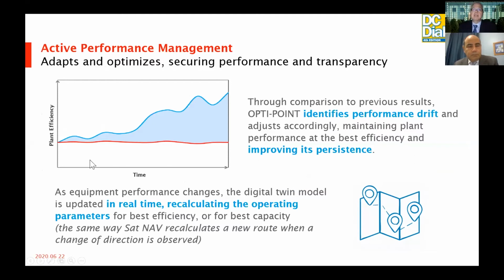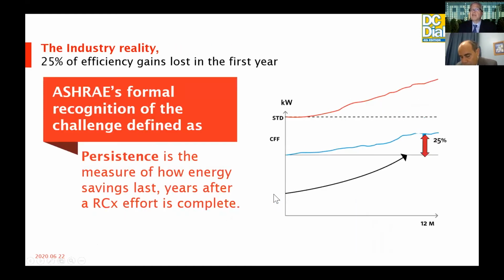One of the biggest challenges that we've seen with any plant is that drift is inevitable. Things happen that the operator cannot be sensitive to without the accuracy and capabilities of a digital twin. We're able to see minute trends and changes in performance ratios. And shown on this blue line would be a traditional plant's operation over time. And it wouldn't be until performance has drifted this far before it's noticed on the output readings for the week in terms of maybe kilowatts per ton. Whereas with a self-optimizing system that learns, it's able to notify the operator, specifically pinpoint them to the right area, and change its course of direction, just like SatNav does when you're in traffic.